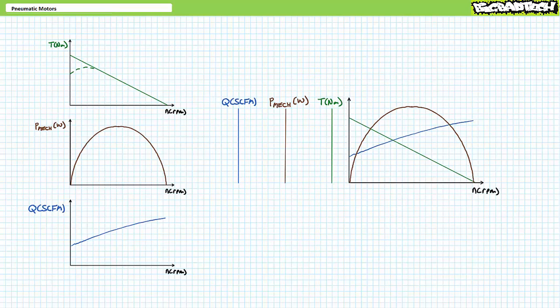To determine torque at a particular speed, one will locate the speed of interest, follow a vertical line until it intersects with the torque curve, and follow it horizontally until it intersects with the torque scale, and then read that data. Same thing for mechanical power. At that speed, follow it up until it hits the power curve, then it goes horizontally until it intersects with the power scale. Same thing for flow rate. At the speed of interest, follow it up until it hits the flow rate curve, then go horizontally until it intersects with the flow rate scale. In summary, it's tight, but usable. We can use this type of chart to determine the motor's operating point, i.e. a condition with a known speed, torque, flow rate, and mechanical power. That's all we need to know, right? Wrong, what about pressure?